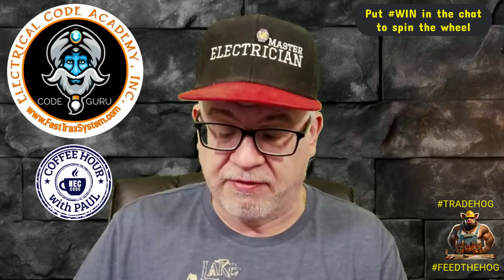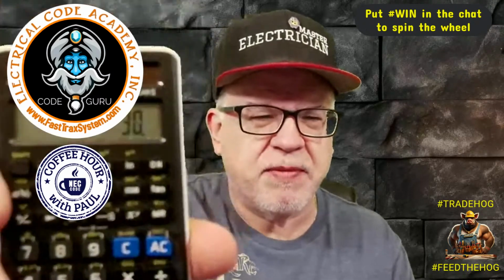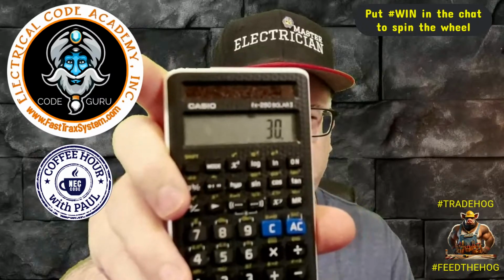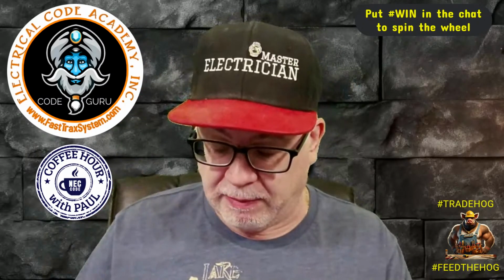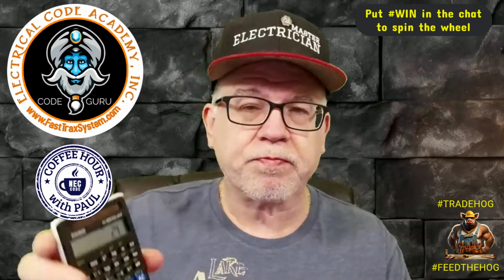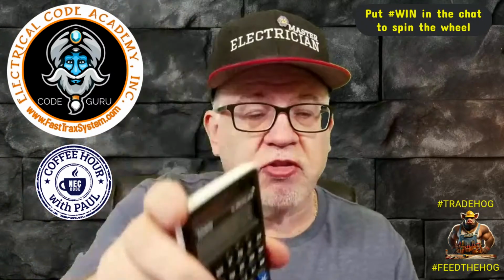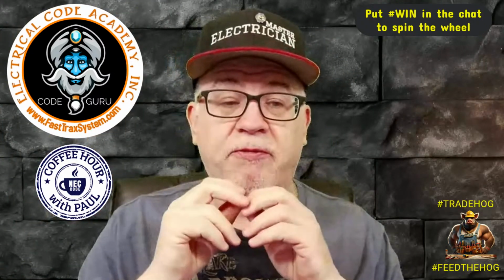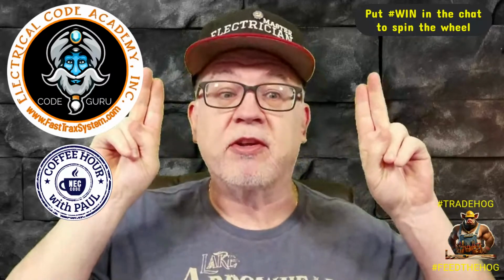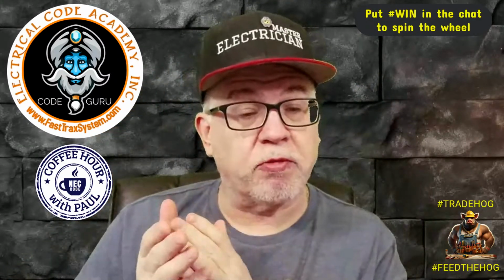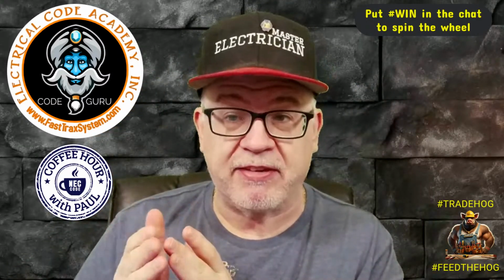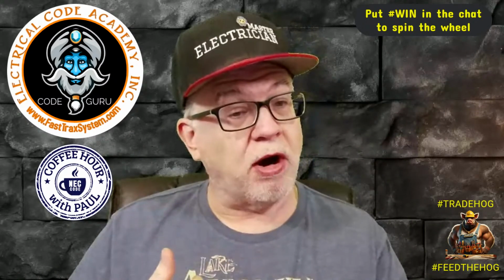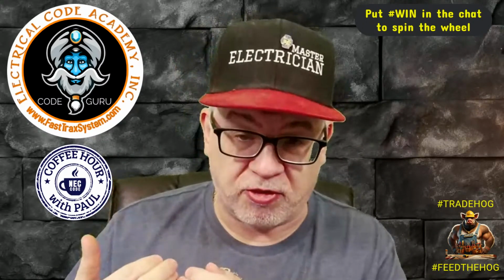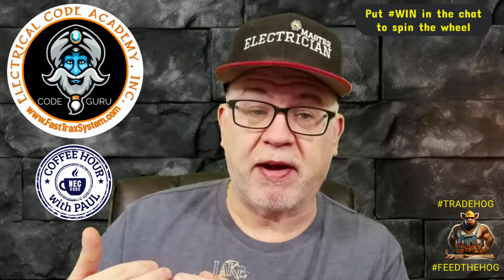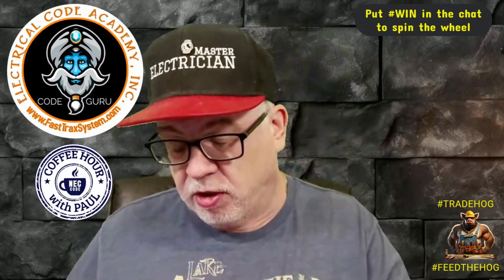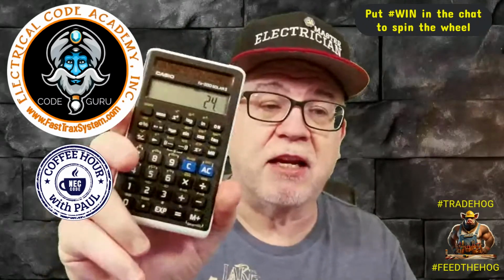So let's say I have a 30 amp breaker. Let's just use numbers. There's the old trusted Casio right there: 30 amps. So it's a 30 amp overcurrent device. I multiply that by 0.80. That's 24 amps. So I can't put more than 24 amps of continuous load, whether it's a load that runs for 3 hours or more at maximum output as defined in Article 100, or something in the code that says treat it at 125% as a continuous load. So in other words, on a 30 amp breaker, I can't load more than 24 amps.